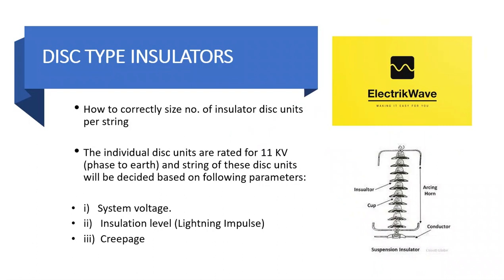Now let's see how to correctly size the number of insulator disk units per string. The individual disk units are rated for 11 kV phase to earth, and the string of these disk units will be decided based on the following parameters: 1. System voltage, 2. Insulation level, 3. Creepage.